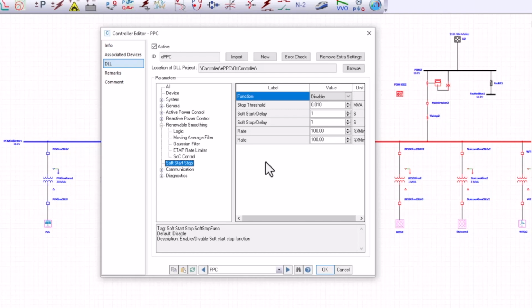Finally, we have soft start and stop of the plant, which ensures a smooth startup and shutdown of the plant based on the command of the operator of the system that originates from the HMI. It can automatically open or close breakers as needed based on the settings that the operator wants EPPC to apply. And these are the core functionalities of EPPC that users need to set for any project.